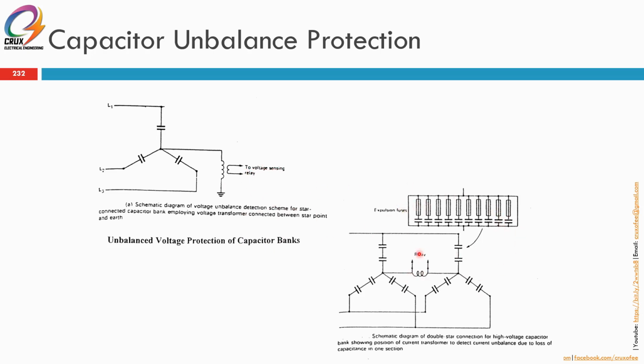This is also another type of unbalance protection, between two star points of two star connected capacitor banks. If any one of the capacitor banks is shorted or open circuit, there will be a current flowing through this relay. If the current is high enough, this relay will trigger overcurrent and trip the capacitor bank. Okay, so this is capacitor unbalanced protection.